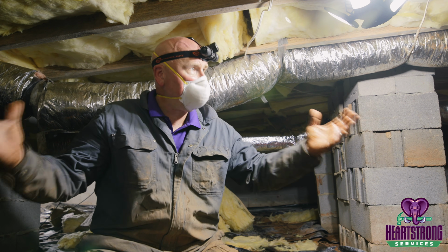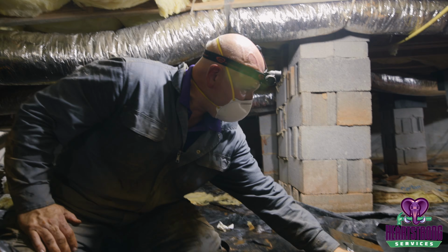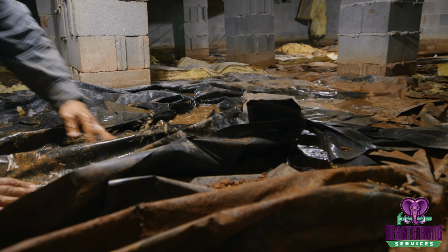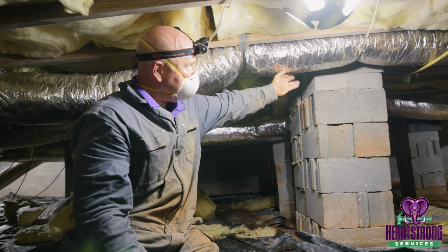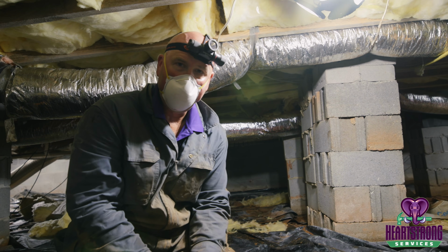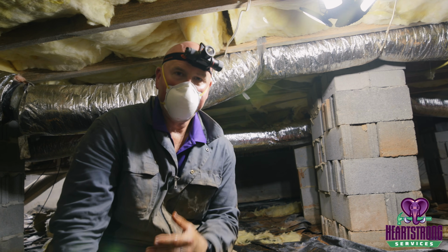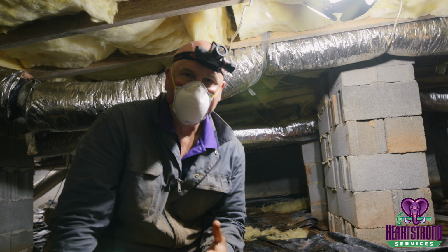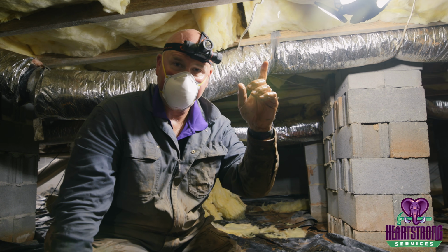Well, it causes the crawl space to get wet, and we can see that with the amount of water standing on top of the plastic here, because it's causing this ductwork to sweat and rain all this condensation because it's the coldest surface down here. Now, part of our evaluation, we can clearly see that visibly, but we also want to evaluate that when that air comes inside, the leading indicator is that the humidity is going to go up inside of the crawl space first.